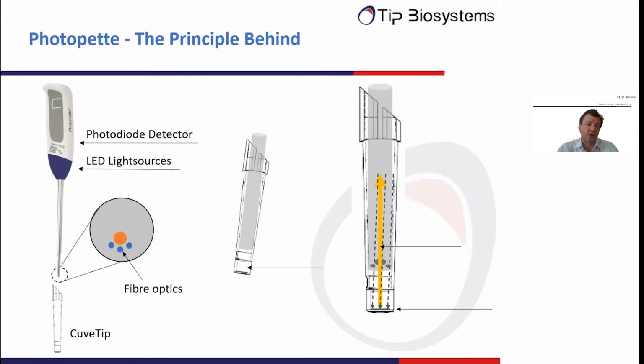So how does the Photopette work? The Photopette here seen on the left is a truly handheld device. It has light sources, which are LEDs, and it has a photo detector, and it's a fiber optic based device. What you also see on the left here is the fiber optics at the end of the Photopette stainless steel stem, and you see the cuvette tip. And in the middle of this picture, you see a bigger view of the cuvette tip attached to the stem of the Photopette device.